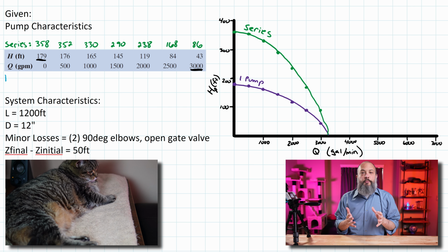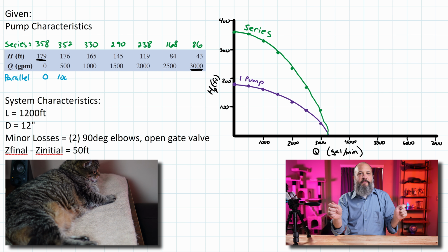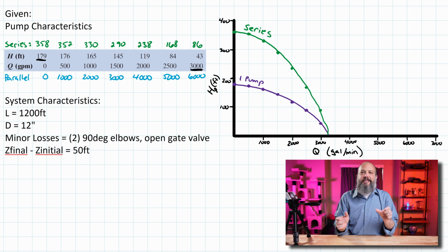And now when you place two pumps in parallel, their entrances and exits are connected, but flow takes a separate path to get from the entrance to the exit, right? Half the flow will go through the left pump, half through the right pump. So in this case, since the entrance and exits are the same, the pump head added by each pump will be identical to each other, but this time flow rate will be doubled, right? If the first pump can pump 500 gallons per minute, and the second pump's also 500 gallons per minute, then combined, they're adding 1,000 gallons per minute at the exact same 176 pump head.